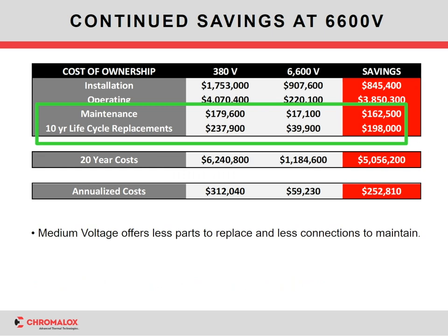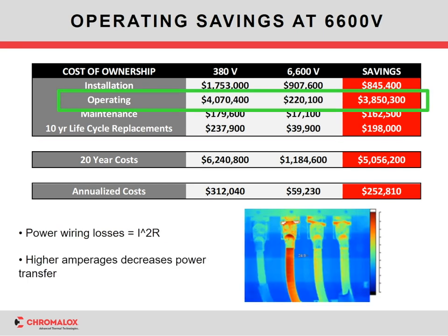And with a medium voltage system versus a low voltage system, the maintenance cost is much lower, simply because there's less connections to maintain, less parts to inspect, and less fuses to worry about changing. Similarly, on the product replacements over the life cycle, there's simply less components to worry about during the life of the product. The other very significant savings with medium voltage comes out in the operating cost. As you can see, we're able to demonstrate to the customer millions of dollars of savings over the lifespan.